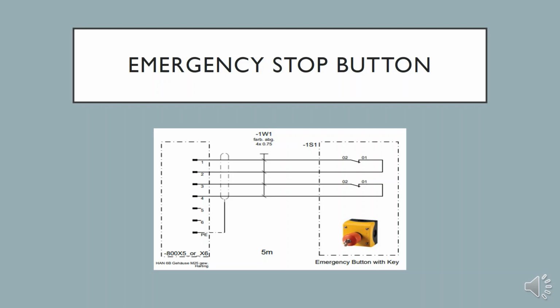For the next slide, I will explain the emergency stop, which works with dual channel operation. It will monitor the discrepancy time between the two contacts and it has cross-short detection to prevent connecting the two circuits together in a fault case. From the circuit, we can see the two switches which are normally closed. They connect from cable 1 and 3 to the emergency button with key.